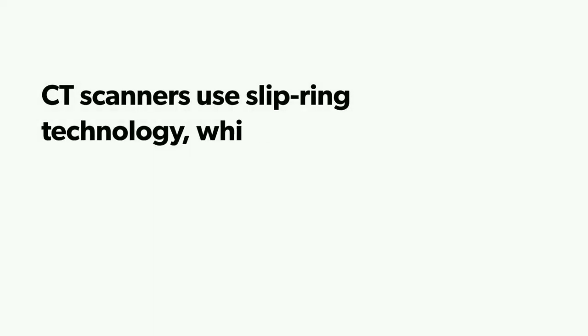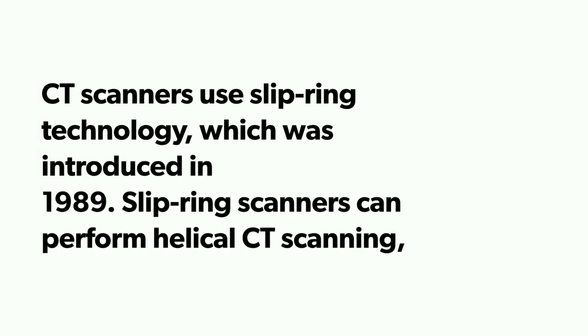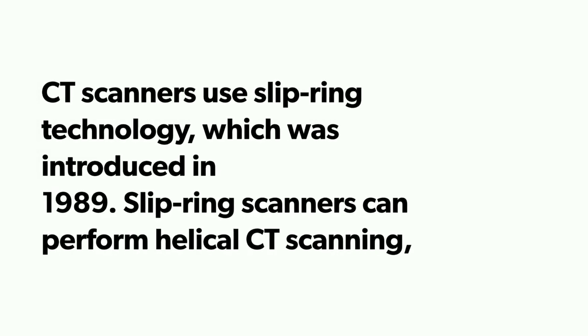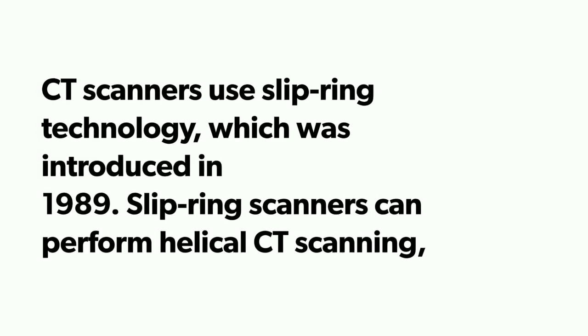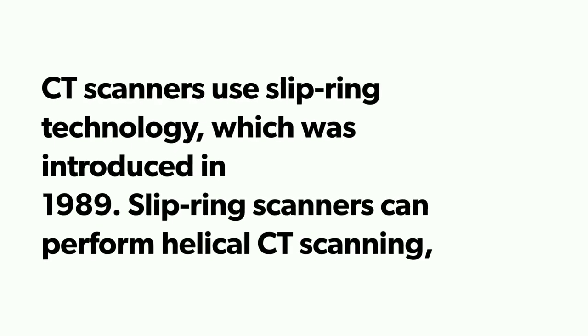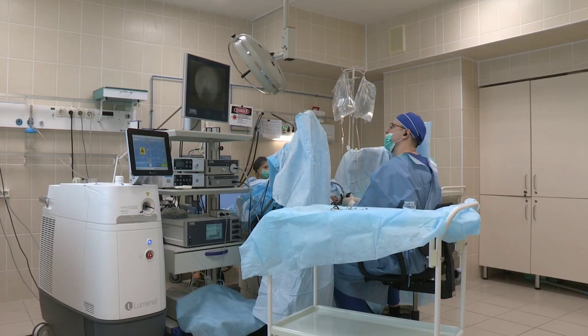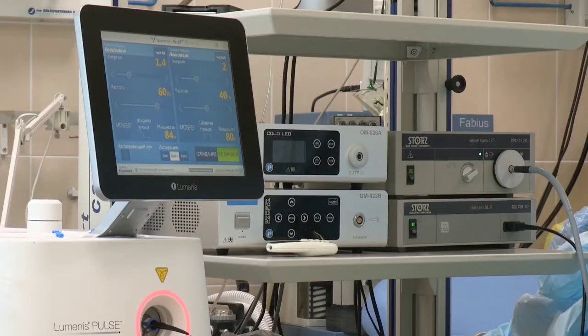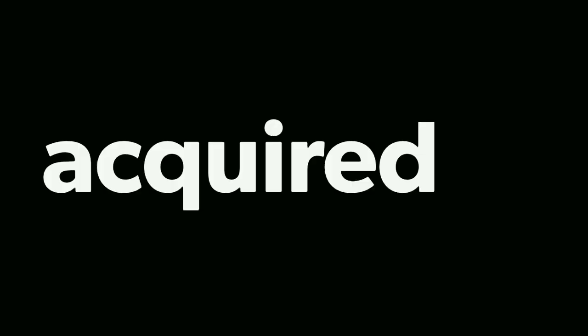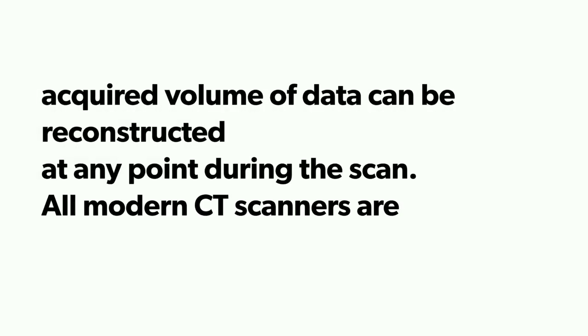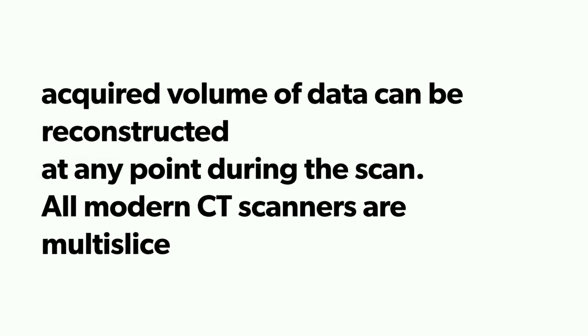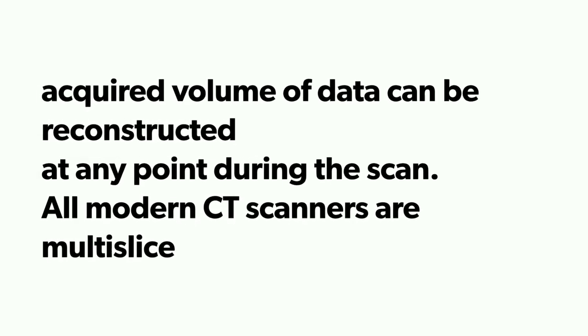CT scanners use slip ring technology, introduced in 1989. Slip ring scanners can perform helical CT scanning, in which the x-ray tube and detector rotate around the patient's body, continuously acquiring data while the patient moves through the gantry. The acquired volume of data can be reconstructed at any point during the scan.